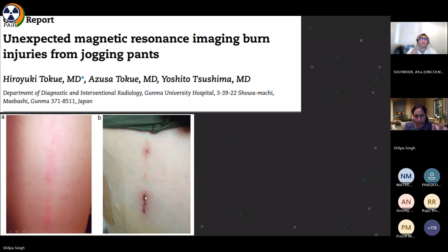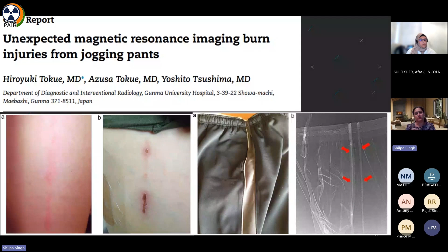It was later checked using the joggers. High resolution digital imaging, a digital X-ray, was performed, and in the digital X-ray it was realized that there was a micrometallic component in the stitching of the trousers, which we are not very sure of. So that was it. This is proximity burning. Whenever we have the MRI bore very close to the patient's body, when we apply the RF energy to the patient, it heats up.